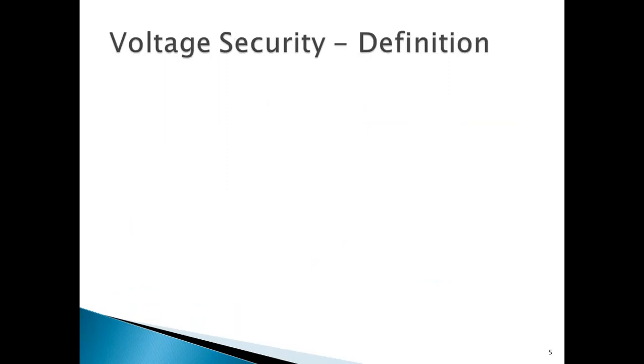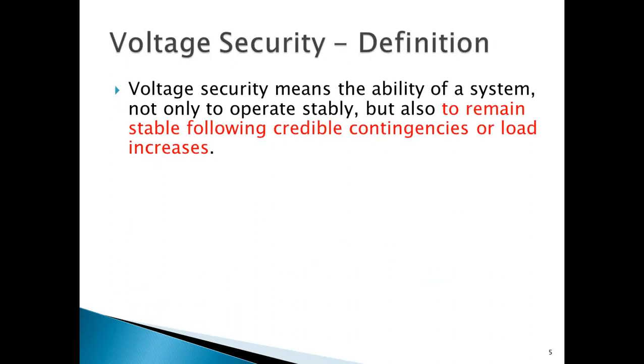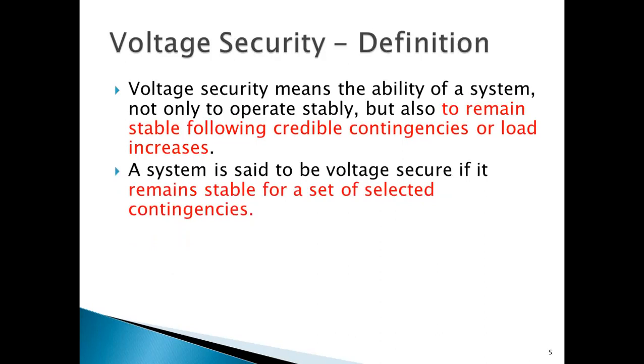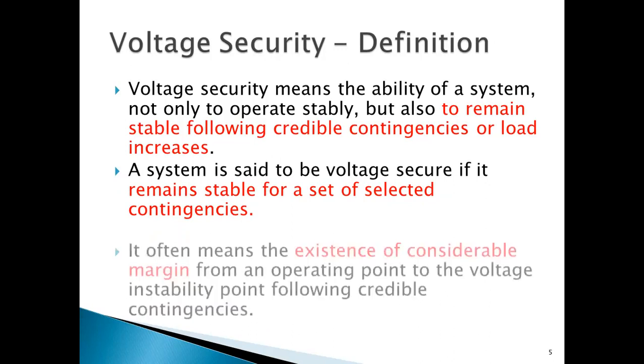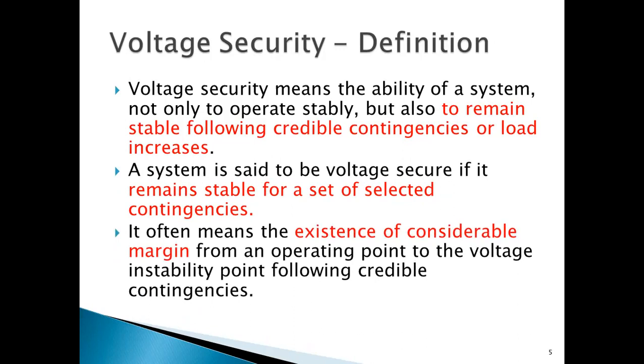Next, let me explain how voltage security is defined. As you see here, it is defined as the ability of a power system not only to operate stably but also to remain stable following credible contingencies or load increases. The credible contingency means severe faults or disturbances. A system is said to be voltage secure if it remains stable for a set of selected contingencies, i.e., outages. It often means the existence of a considerable margin — the distance between the current operating point to the maximum loadable limit or voltage instability point following credible contingencies.